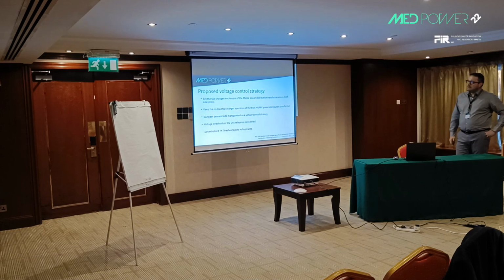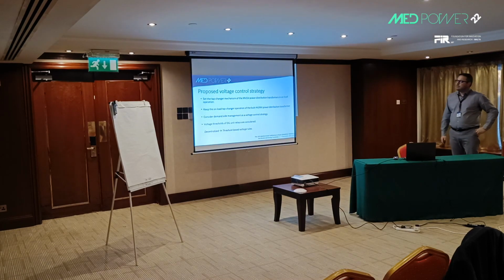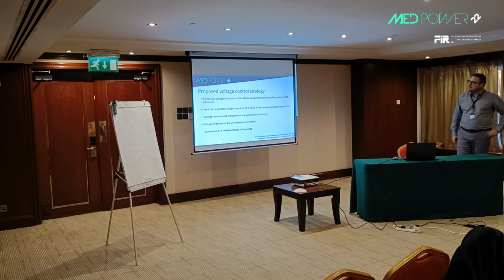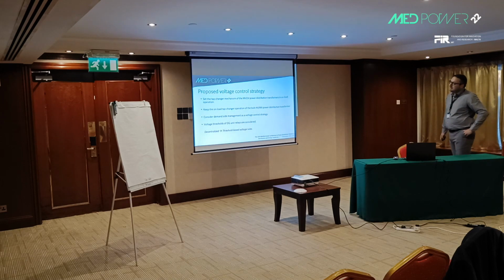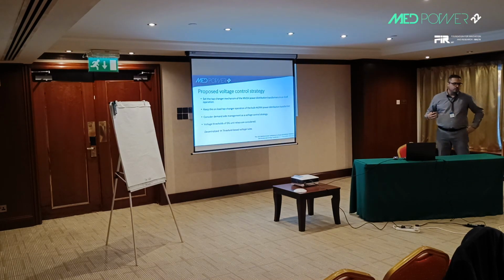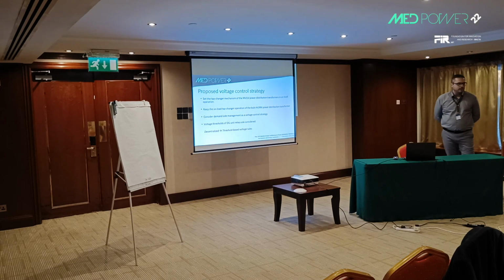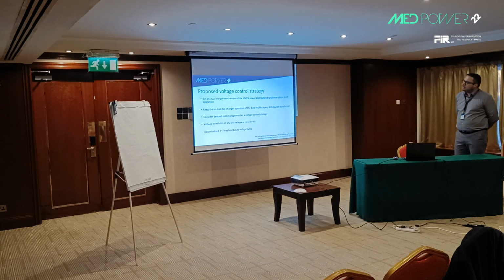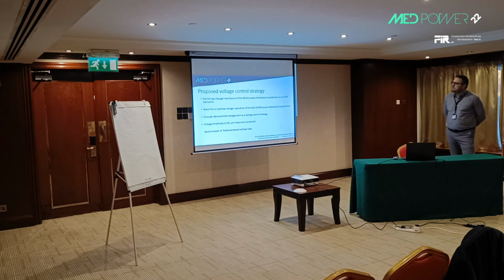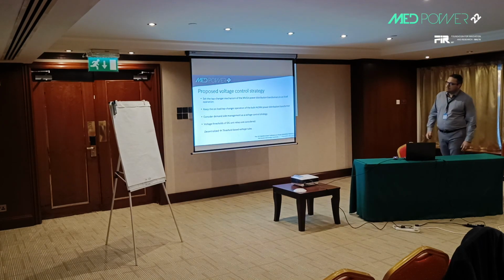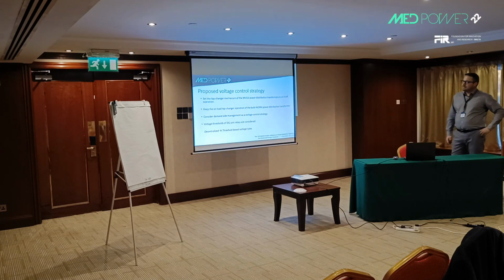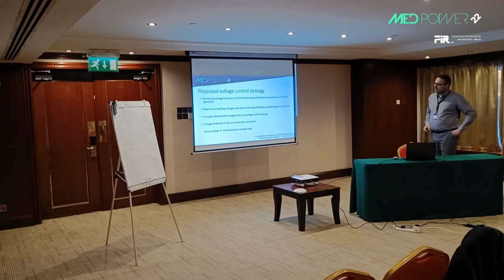Moreover, we consider voltage protection of DG units because, although DG protection is important for the integrity of the DG unit itself, from the viewpoint of the distribution system operation, if there is an unintentional trip of a DG unit, this of course deteriorates the system operation. The control strategy is based on threshold-based voltage criteria, and it is fully decentralized since the only requirement is local voltage measurements.